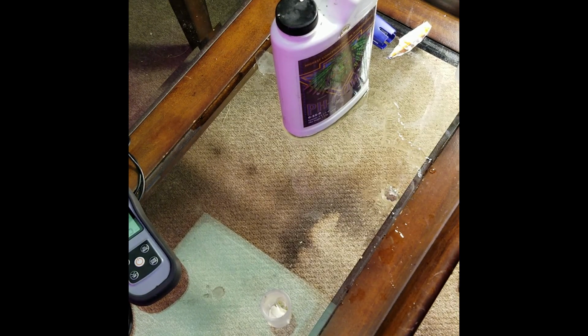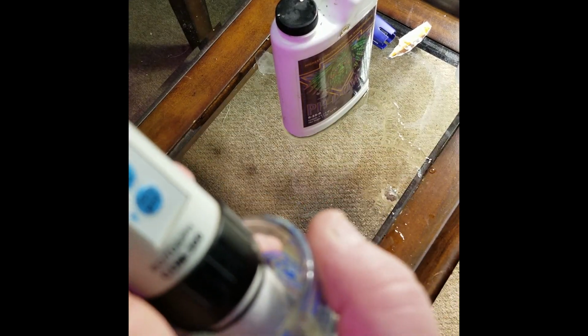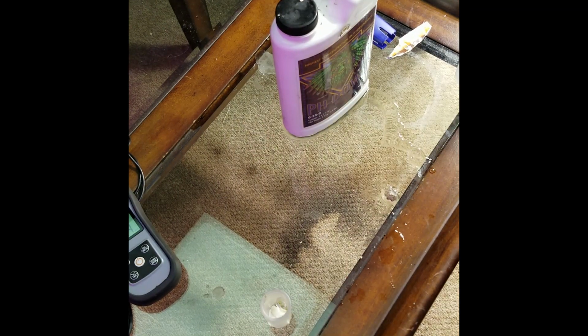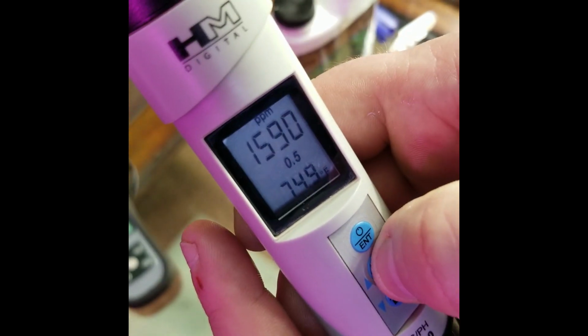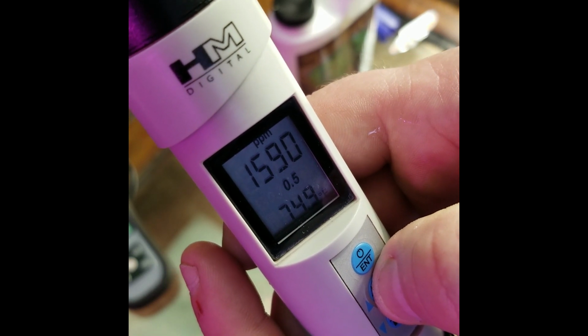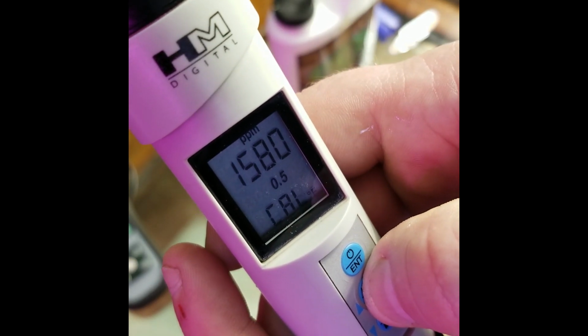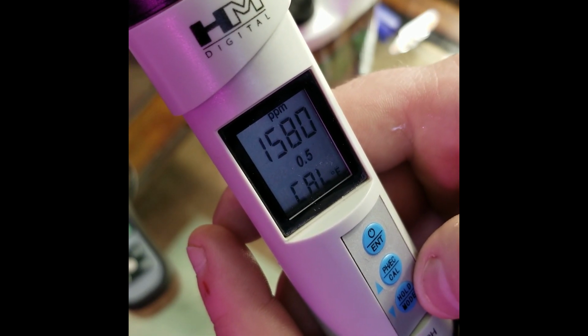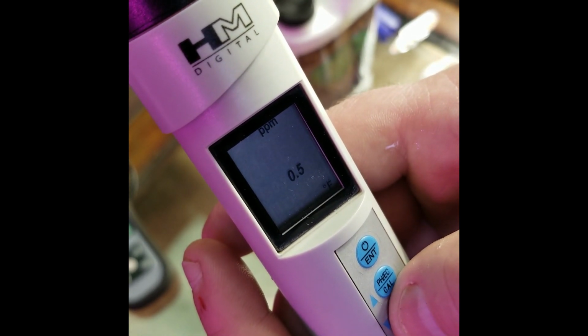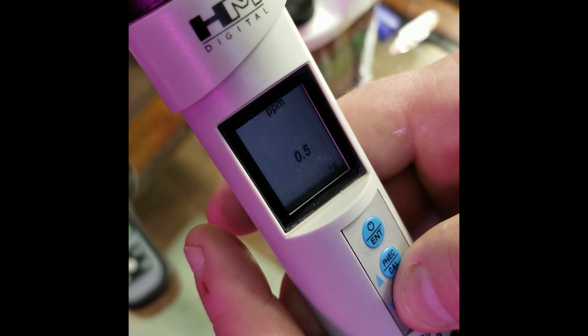Let me add more solution. Because yeah, you can see the pins on this meter are a little bit higher than the pH probe. So you have your pH and your temperature down low, but the pins on this one are definitely a lot higher, and with me tilting it to try to film it. So it reads 1590, so we're going to do this calibration again, maybe even a third time. And you do have to sometimes do this to get these meters really to be consistent. So we're going to use our down button to go to 1580.